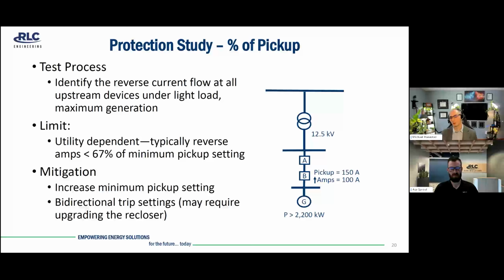So if we look at the example over here on the right, we have a midline recloser labeled B. The minimum pickup on that was 150 amps, which means anything approximately 100 amps or less would pass, and anything more than that would fail. And just as an idea of size, on a 12.5 kV circuit, that's about 2.2 megawatts of generation. So it doesn't take a whole lot stacked up behind some of these devices to push you over that minimum pickup.